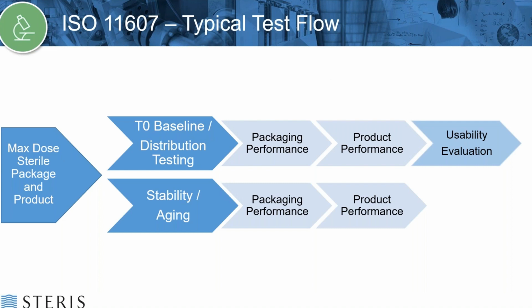So, typical test flow for ISO 11607, max dose sterile package and product. Again, you're going to want to run these samples through that max dose. So radiation is at or above the maximum routine dose that your product might see. If it's going through ethylene oxide, it's going through 2x or 3x sterilization, whatever it is that you're validating as part of your sterilization validation. So you're going to do some baseline testing, and the distribution testing is often considered the baseline. So you can have separate baseline samples as well if you prefer to go that route.